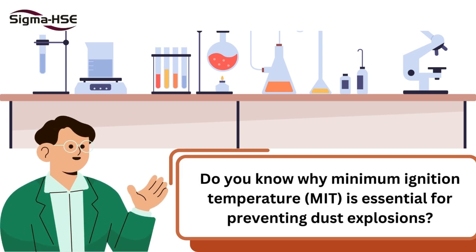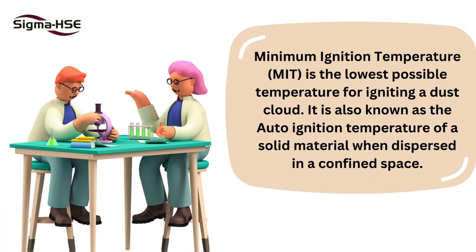Do you know why minimum ignition temperature is essential for preventing dust explosions? Minimum ignition temperature is the lowest possible temperature for igniting a dust cloud. It is also known as the auto-ignition temperature of a solid material when dispersed in a confined space.